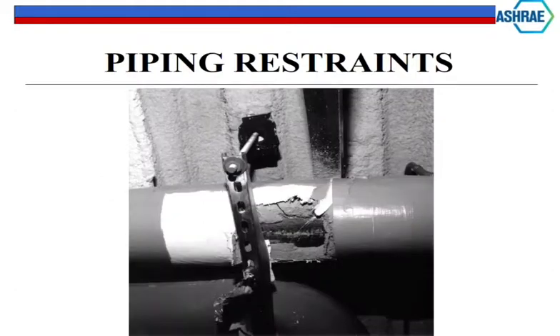So this is one of the photographs I wanted to show you. During the earthquake, this is the insulation. It had an insulation shield, which is a piece of sheet metal. As it started to move, it fell out. All of these here are scratch marks on the bottom of the pipe from that steelwork. That's how much this thing moved back and forth and scratched the bottom of this pipe. It ended up back almost exactly where it started, basically back in the center.